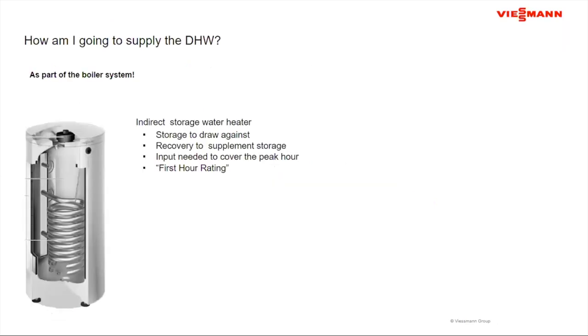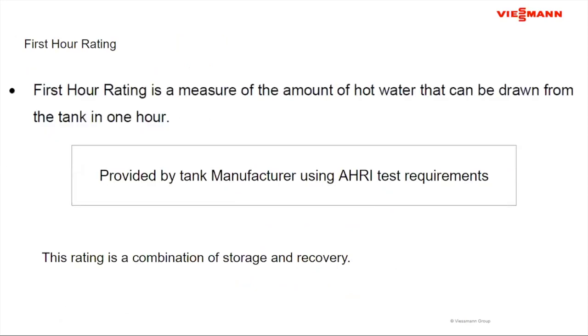Now, when I shift over to a storage tank indirect water heater, things start to change, because now it's about storage, but it's also about recovery. With a storage water heater, I'm not primarily focused on what's required during the peak minute, but usually the peak hour. How do I combine the storage and the recovery to meet the demands of that boiler over what's referred to as the first hour? When we look at boiler indirect water heaters, we talk about first hour ratings. The first hour rating is a measure of the amount of hot water that can be drawn from a tank in 1 hour.